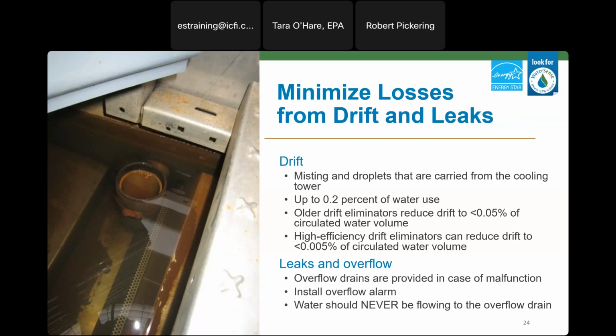The other maintenance item to be aware of is the cooling tower overflow. Most towers are equipped with an overflow drain that prevents them from being overfilled in the event of equipment malfunction. If the level sensor or a fill valve or makeup valve in the tower fails, this can cause an overflow to the drain without the facility staff realizing it immediately. The photo on the slide is of a tower basin where the fill valve controlling the makeup water was stuck partially open. Water was constantly flowing, overfilling the basin and going down the drain.